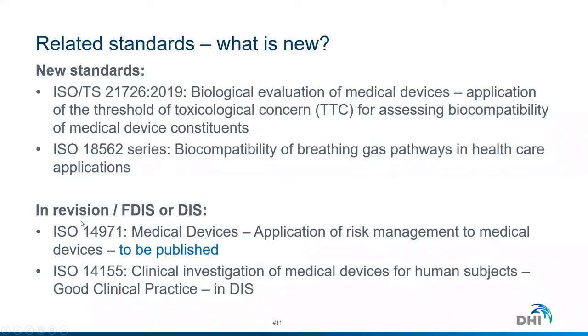Then there are two important standards that are related to biocompatibility that are under revision and being updated. The one is ISO 14971 on the application of risk management to medical devices. That is now approved as an FDIS and will be published by ISO these days. I had news that it's now available as an ISO standard.